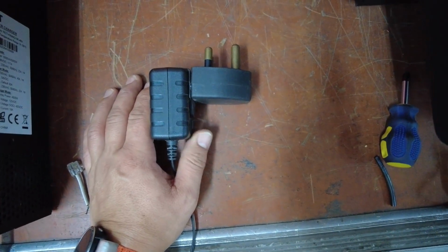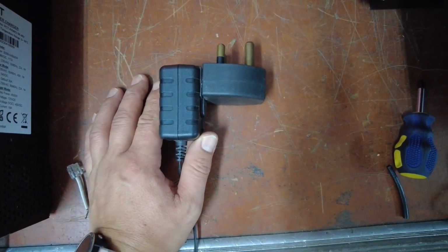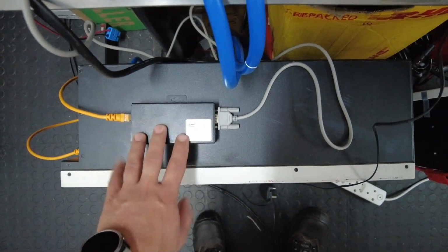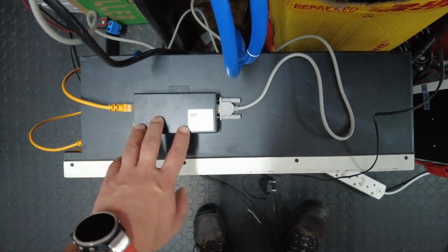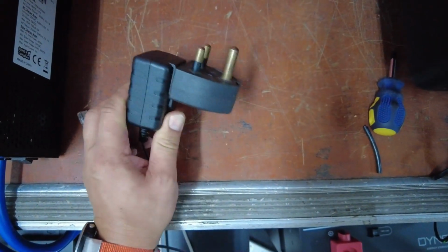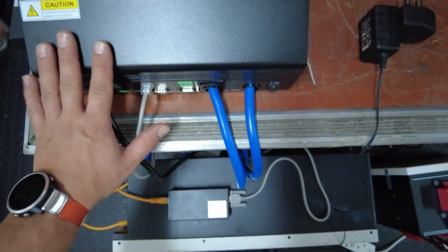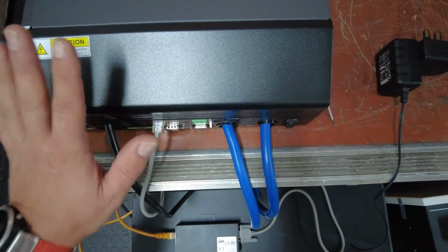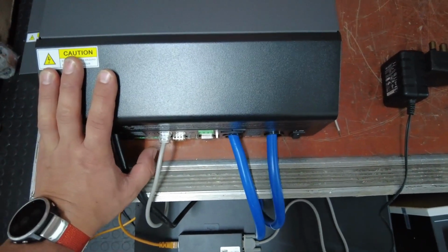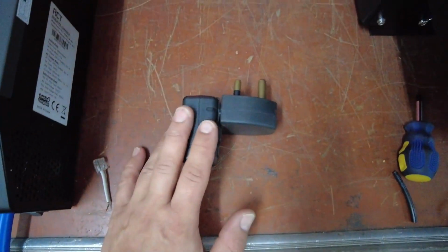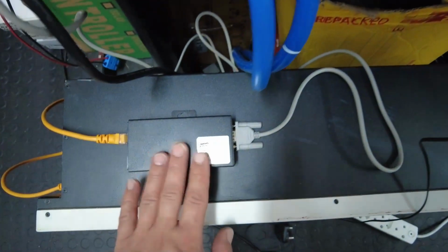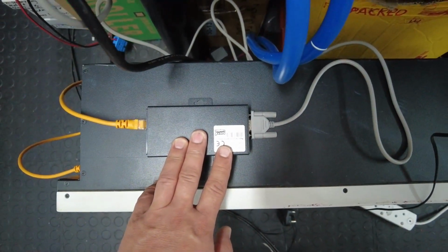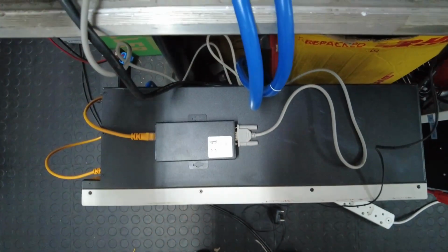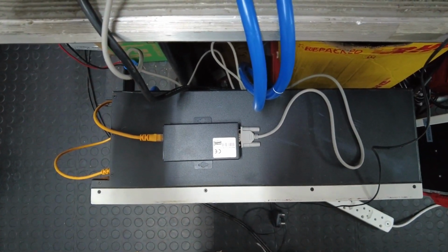Next is the 12 volt DC power supply. Keep in mind, if power from this supply is lost to the BMS box, you will lose BMS communication because the BMS box has no power. So you need to connect this to the output power coming from the inverter. As long as the inverter is operational and providing output AC power to this power supply, there will be power leading to the BMS box, which ensures communication between the inverter and the battery.